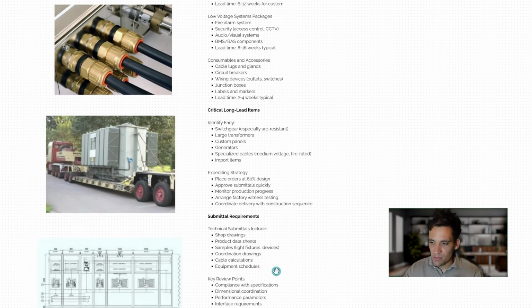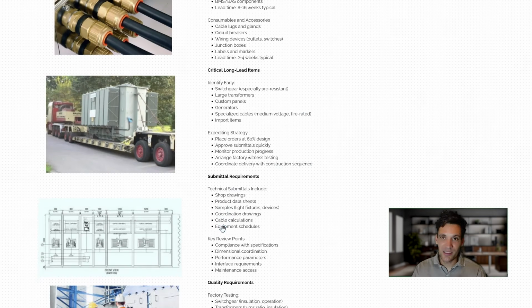Now, depending on the complexity of the equipment, vendors will typically need to provide you shop drawings, data sheets that you need your designers to approve, samples for light fittings or anything with some sort of architectural element, coordination drawings, calculations, and equipment schedules. We would want all this documentation reviewed before we place any orders. Typically, we want our designers to review it and make sure everything's going to work, because the vendor specifications on the product, unless it's purely custom made for your project, are always going to be slightly different to the design. So it's essential for ordering anything that the design team checks it off and approves the shop drawings.